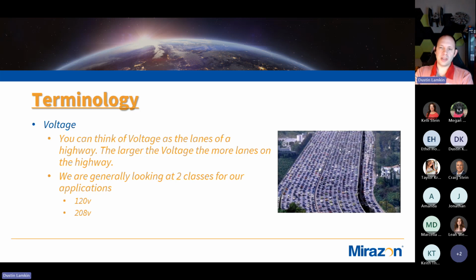Voltage is what you can think about as lanes on a highway. The larger the voltage, the more lanes there are on a highway, right? In normal uses for what we're going to be talking about today, we're referring to 120 volts and 208 volts. 120 being common with American homes, 208 a lot more common in data centers and high power equipment. You still will have 120 volts in your data center. There's generally one thing in everybody's rack that still needs 120 volts, or those little NEMA 5-15 outlets. So we just need to pay attention to what voltages we're using where.